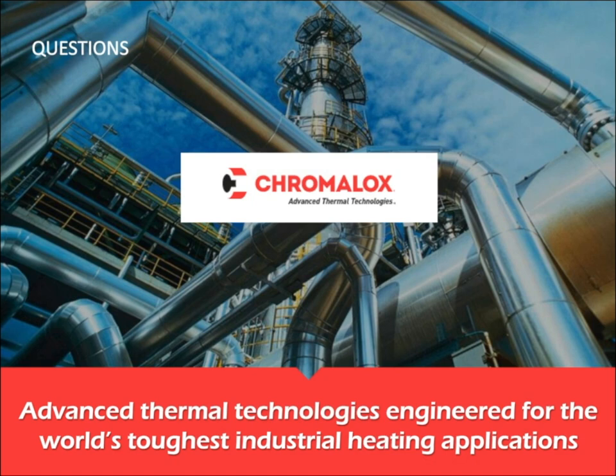So when that's measured, yes, there's some distortion, but it's very minimal. In fact, there's a European norm for the EMC standard, electromagnetic compatibility, and it more than meets that, so we can put CE marking on it if needed. There's also IEEE 519 that's a standard as well, and when you use that phase angle firing, it's well below the allowances in that system. So that's only for a startup condition, but at the full operating loads, we're operating at zero cross, so any issues with harmonic distortion go away.